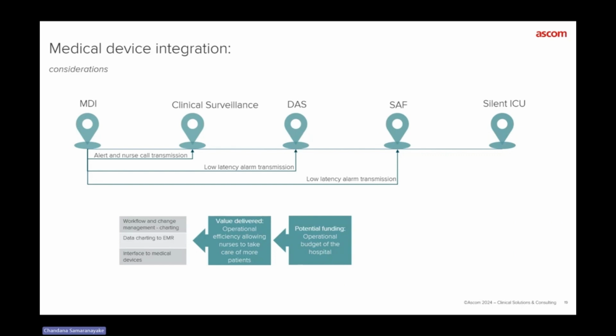So the IEC 60601-1-8 standard, which governs distributed alarming systems, states that the alarms need to get from the bedside device to a caregiver's mobile phone in less than 10 seconds. So there, every second counts, because there's also processing in between. There will be filtering in between.